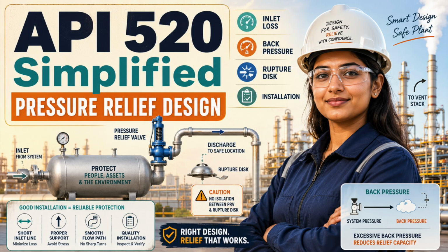It can allow the pilot to sense true system pressure upstream of a restrictive inlet line, but it does not remove the restriction itself. The main valve still receives flow through the physical inlet path. Capacity can still be reduced, pulsations can still develop, cycling can still occur. Remote sensing can correct where pressure is measured. It cannot repeal fluid mechanics.